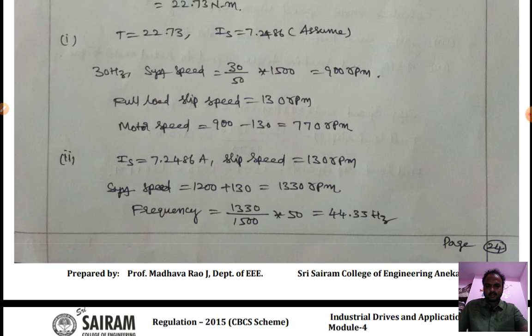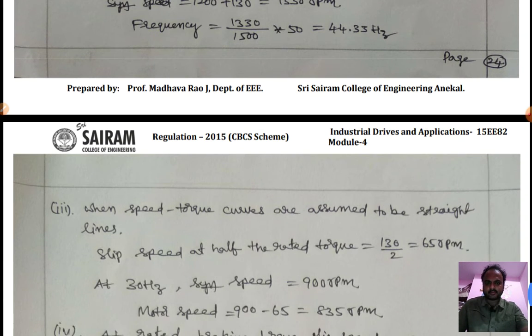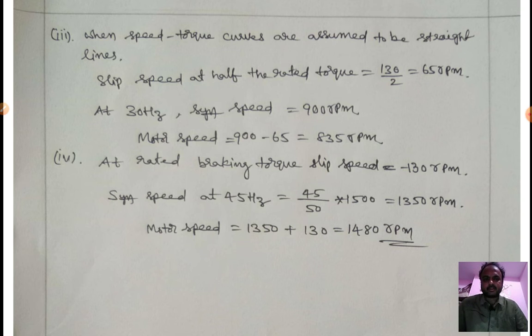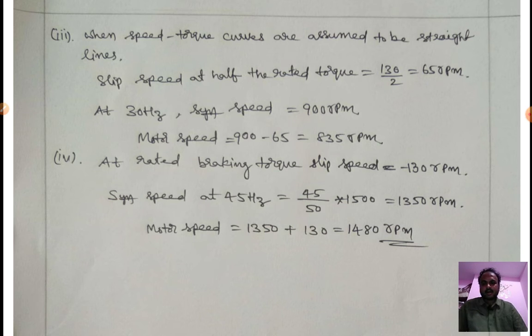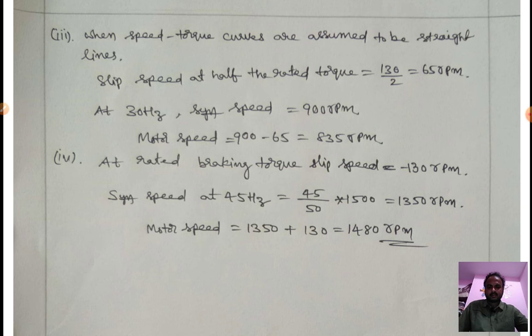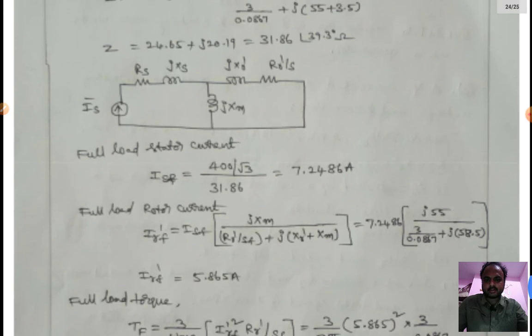For part two, frequency is 44.33 Hz. Since speed-torque curves are assumed to be straight lines, slip speed at half of rated torque = 130/2 = 65 rpm. At 30 Hz, synchronous speed = 900 rpm, so motor speed = 900 − 65 = 835 rpm. For part four, at rated braking torque slip speed = −130 rpm. At 45 Hz, synchronous speed = 1350 rpm, so motor speed = 1350 + 130 = 1480 rpm.